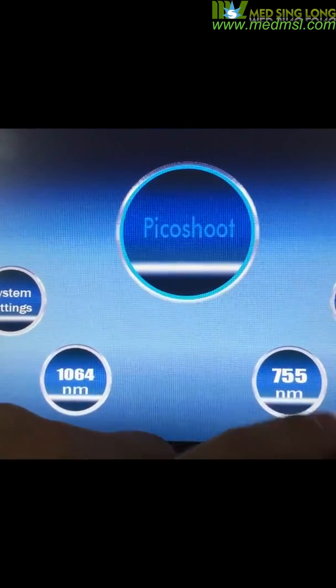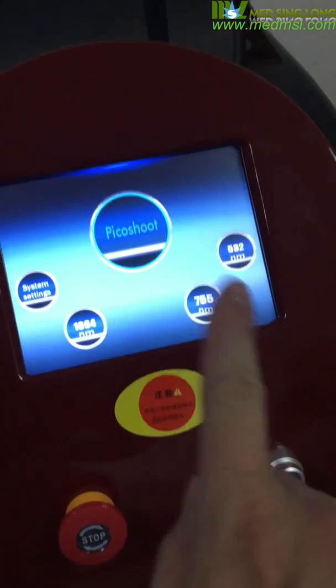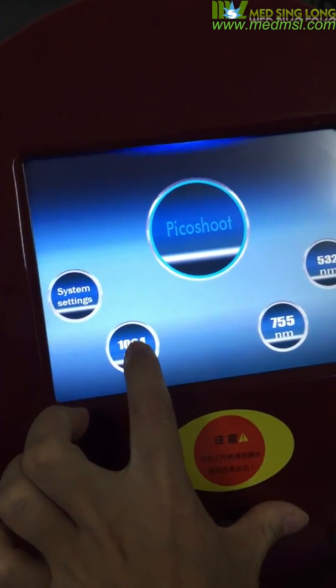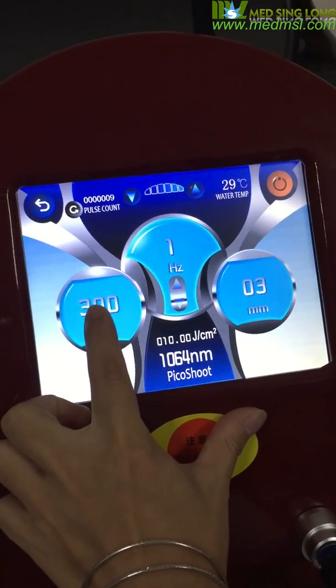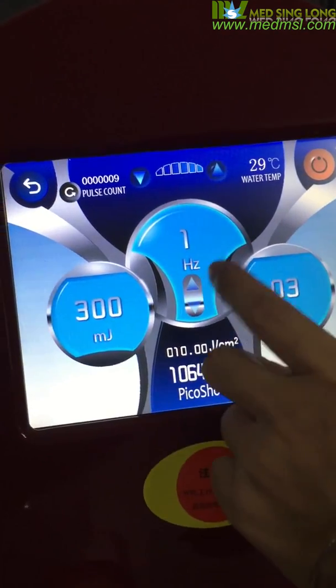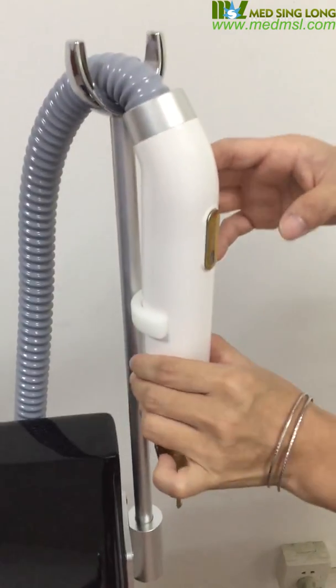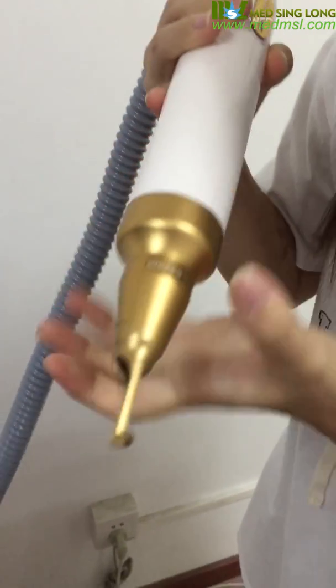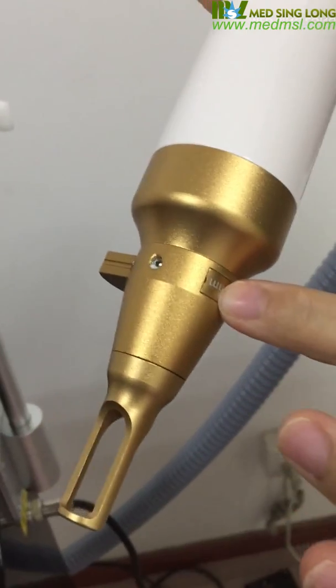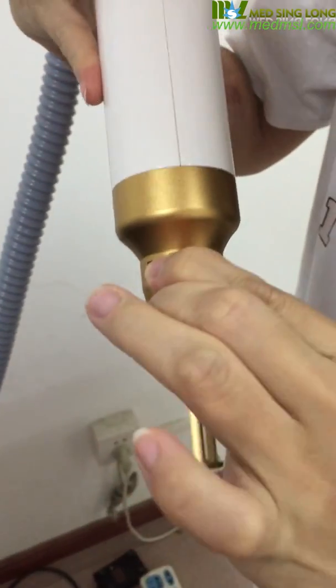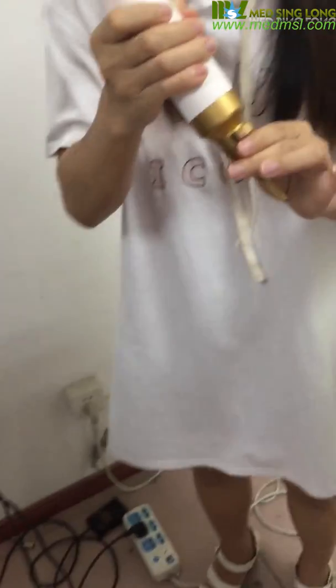The 1064 wavelength is for deep colors like black and dark blue pigmented tattoos. The 532 is for colored tattoos like yellow and red. The 755 is mainly for skin rejuvenation. For picosecond treatment, energy can be set from 200 to 300, frequency is 1, then press work and start treatment. This handpiece can be switched between 1064 and 532 modes for treatment.